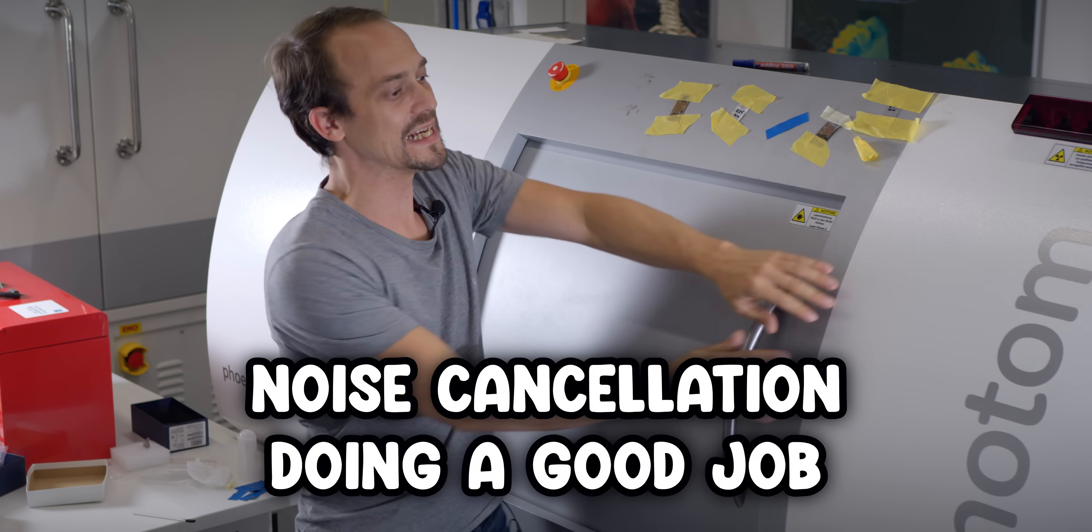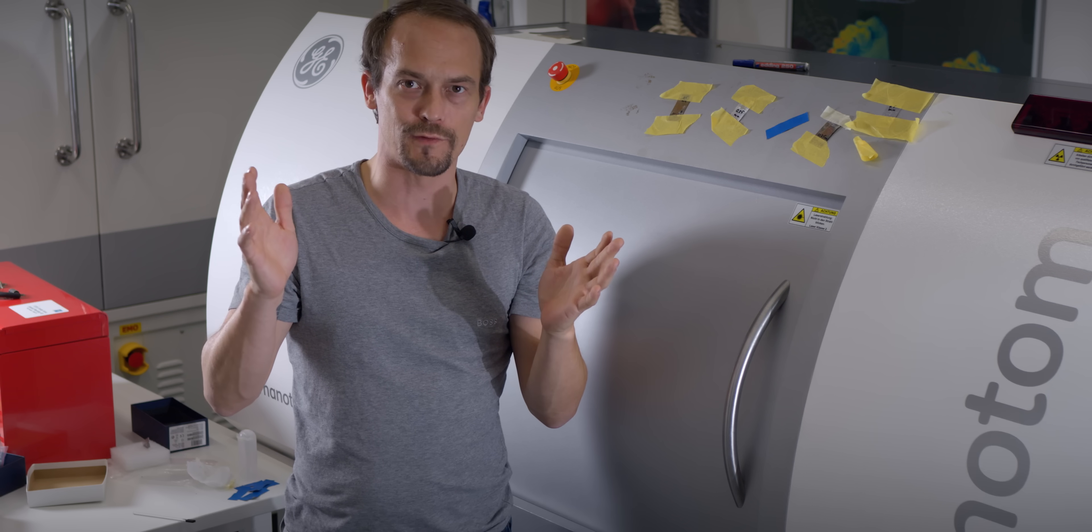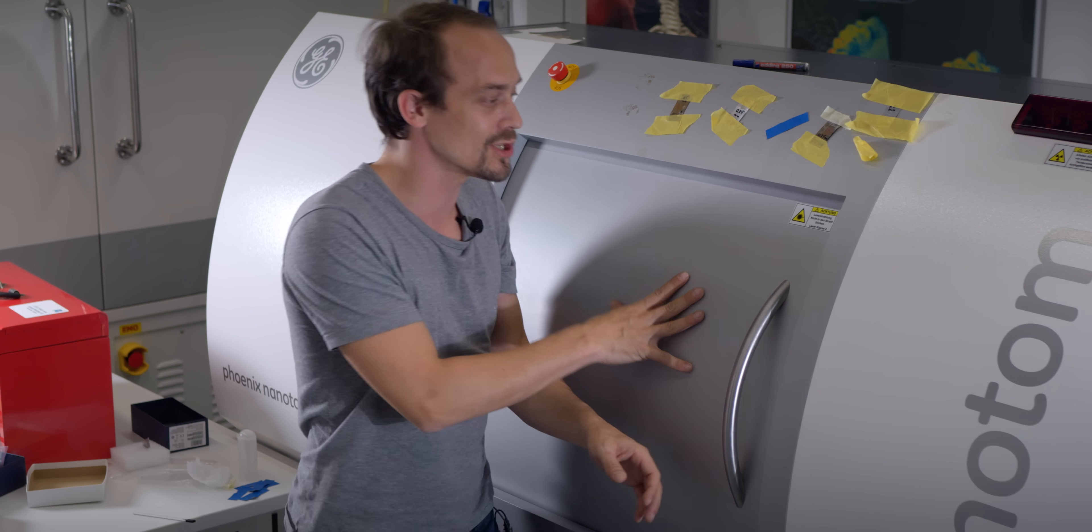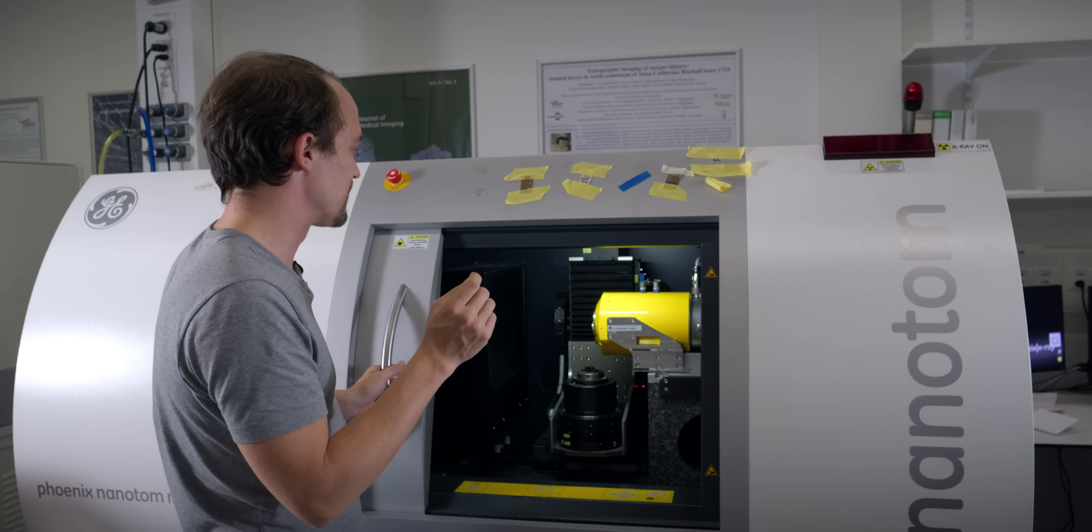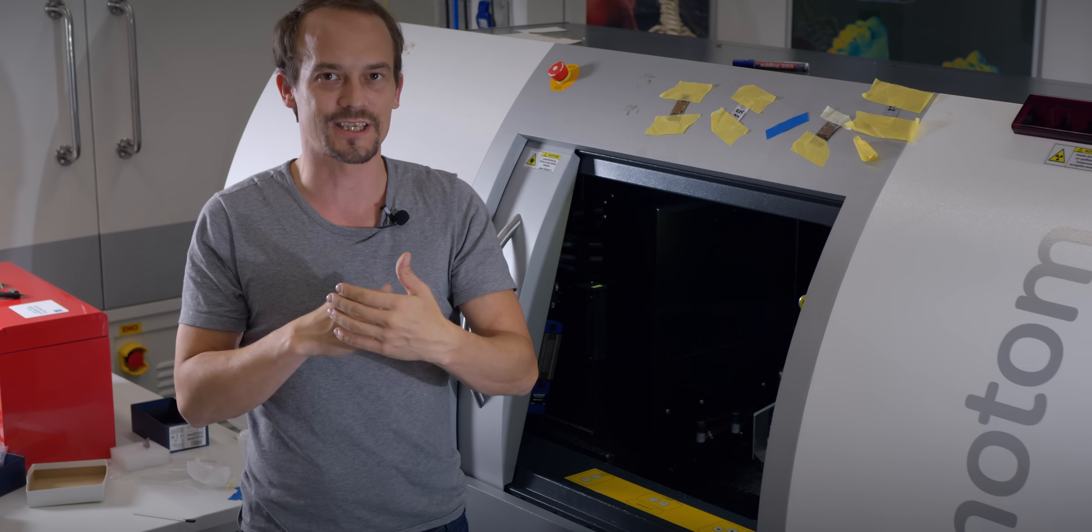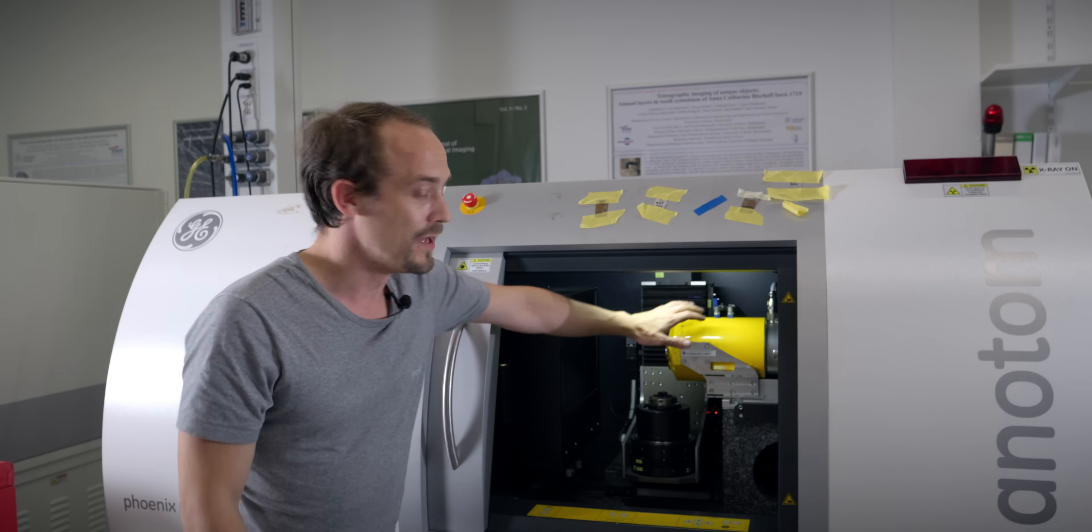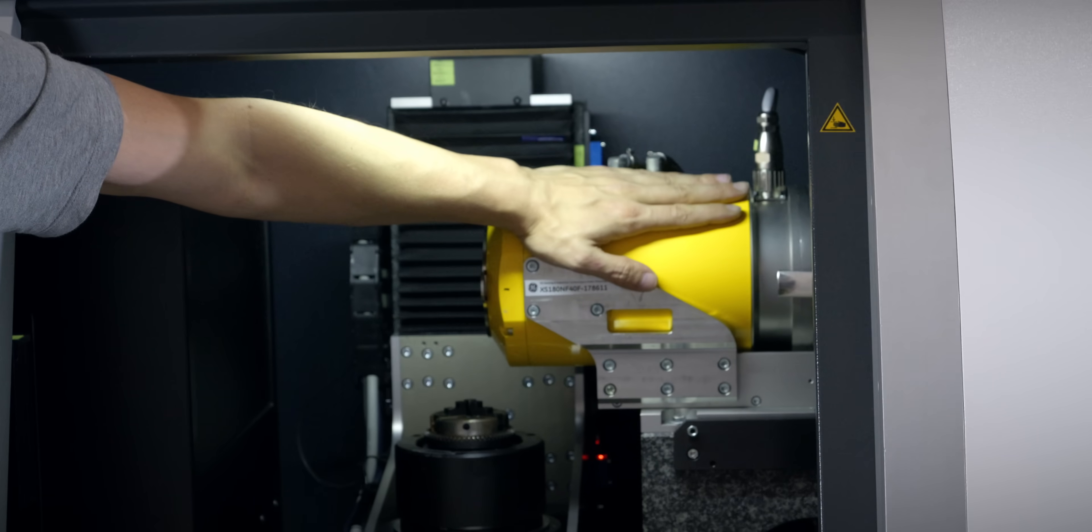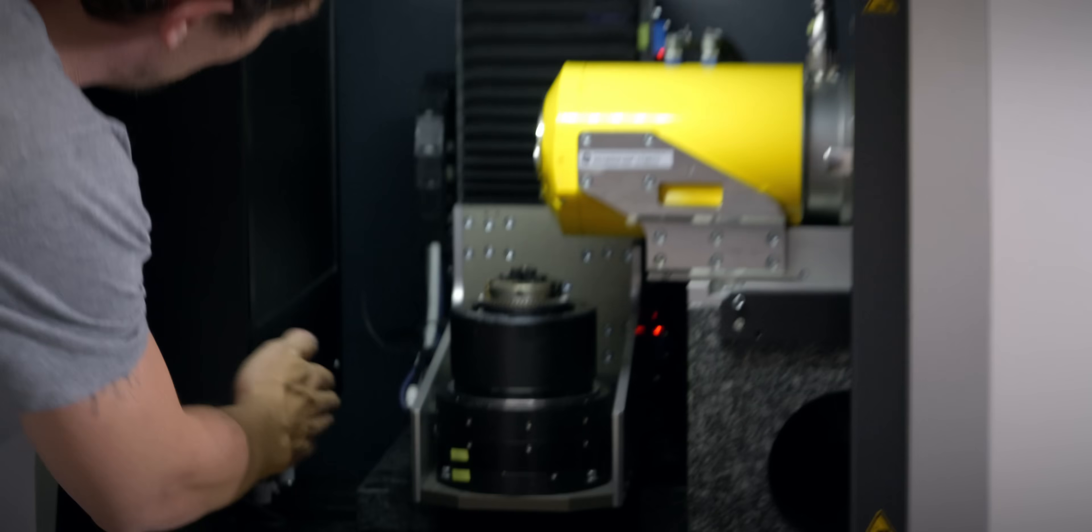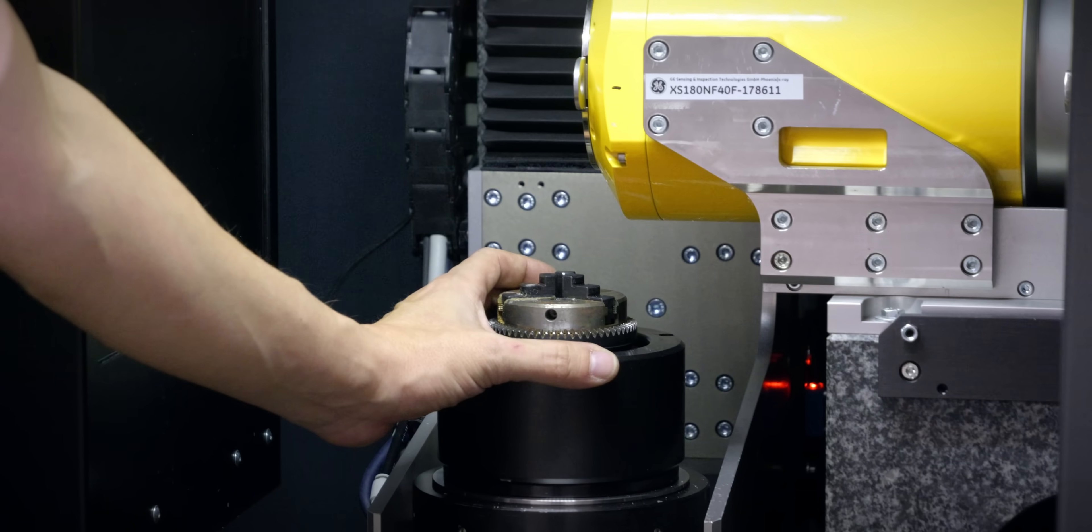So I have to speak up a little bit because in here it's quite loud because of all the cooling of the machine. So this beauty here is called the Nanotome. It's an x-ray machine with magnification. You know if you break your skull or your leg, you have to go into CT imaging. This machine is basically a CT imager for microstructure. I already showed you in my video about medical 3D printing. There I used a cone beam CT where actually there was a cone of x-rays emitted and caught on the other side by a detector. This machine is actually exactly that. You can see here this is our CT tube or our x-ray tube. That's where all the x-ray is produced. On this side here we have our detector. It kind of looks like a screen. And here is my space for whatever I want to look at.